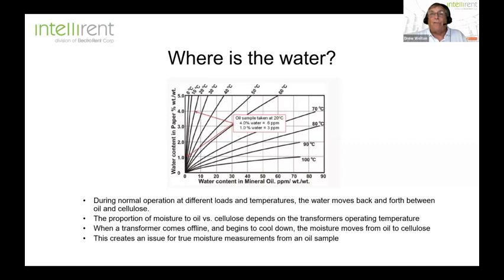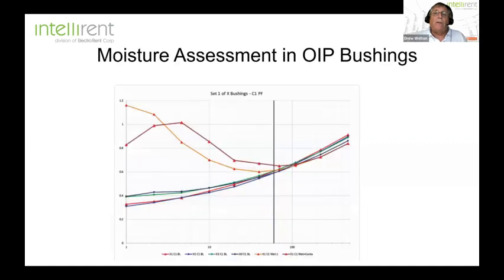There's a lot of reasons for taking bad samples. You didn't draw off enough oil. You had moisture ingress from the time you took the sample to the laboratory. It doesn't take much to create a distortion. There was a period of time where we went out and did an experiment. We went to a transformer, drew off 5 oil samples, and sent them all off to 5 different labs. The ppm measurements that came back were dramatically different. So what do we do in terms of good moisture analysis?